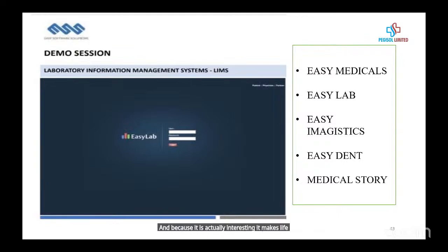It helps to manage your quality system. It helps to gather the information from the pre-analytical to the post-analytical. It also helps you reduce errors, whereby instead of typing your result manually, the equipment can transmit. You can use the barcode system. You scan the barcode, and after programming it at the pre-analytical session, the equipment automatically picks the test that should be done. When the test is analyzed, it transmits it back to the LIS without you having to type, which can save a whole lot of time.